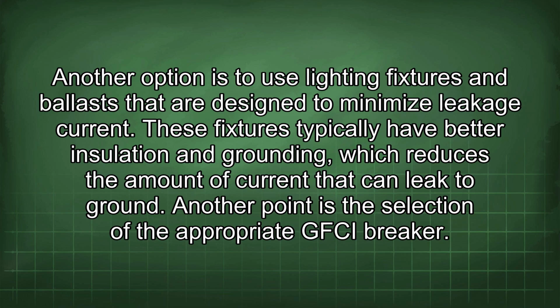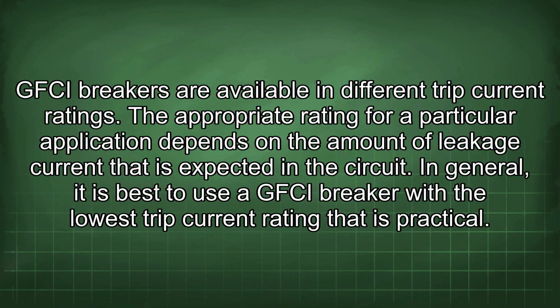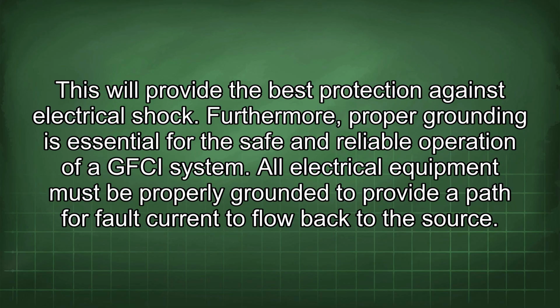These fixtures typically have better insulation and grounding, which reduces the amount of current that can leak to ground. Another point is the selection of the appropriate GFCI breaker. GFCI breakers are available in different trip current ratings. The appropriate rating for a particular application depends on the amount of leakage current that is expected in the circuit. In general, it is best to use a GFCI breaker with the lowest trip current rating that is practical. This will provide the best protection against electrical shock.